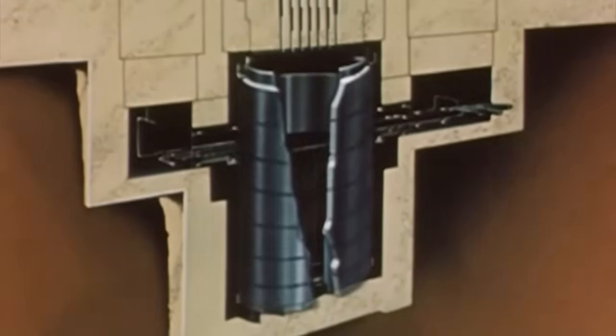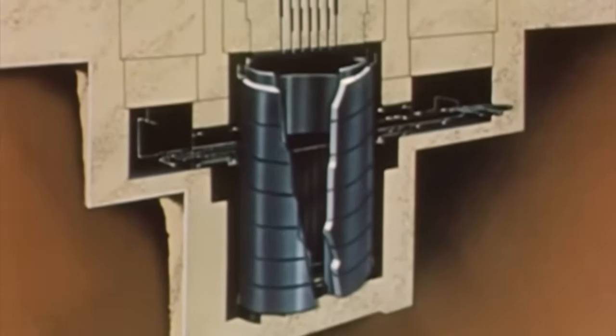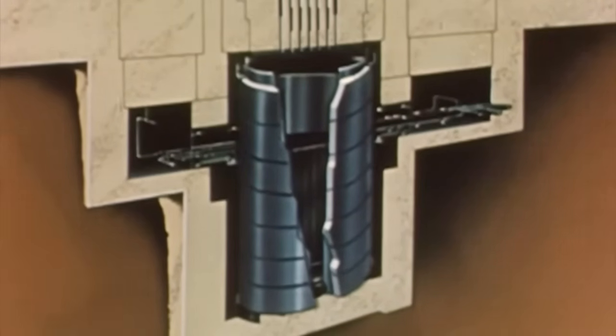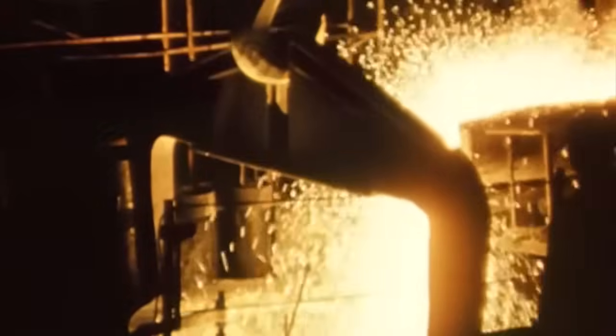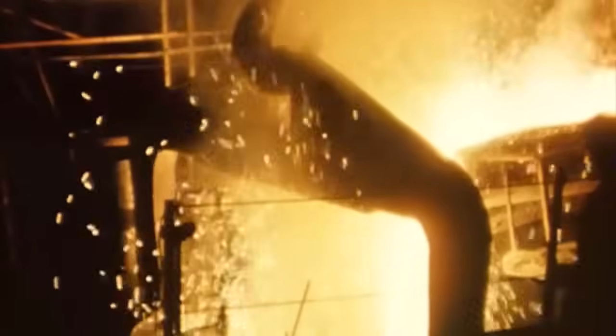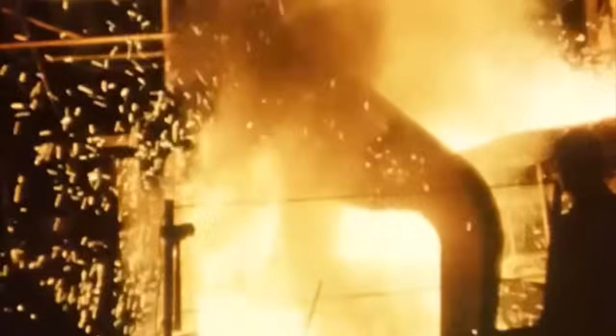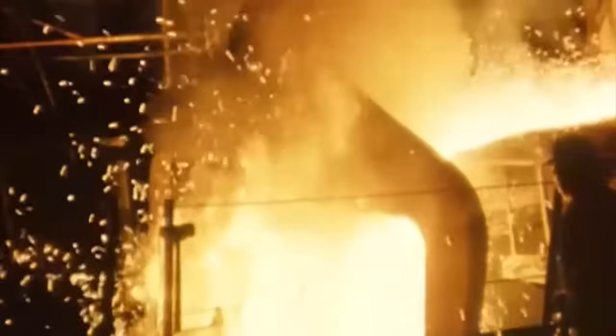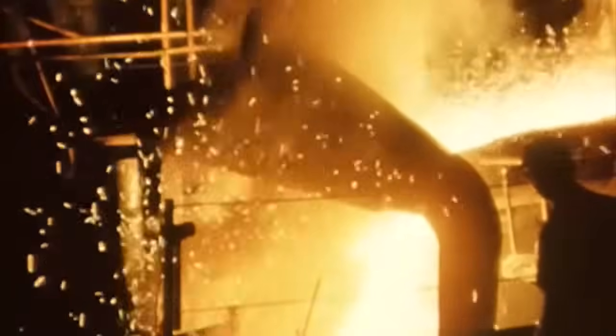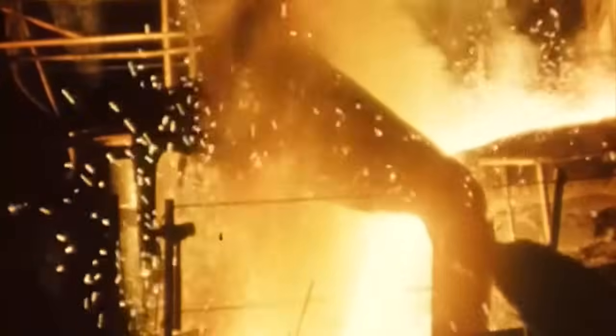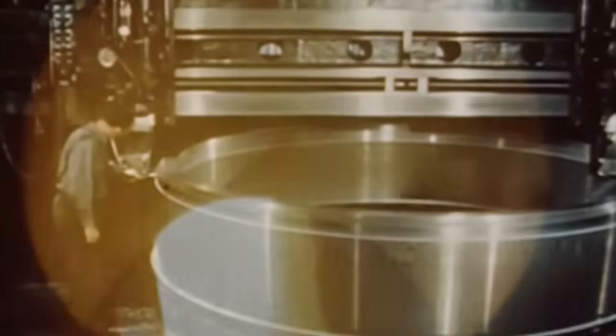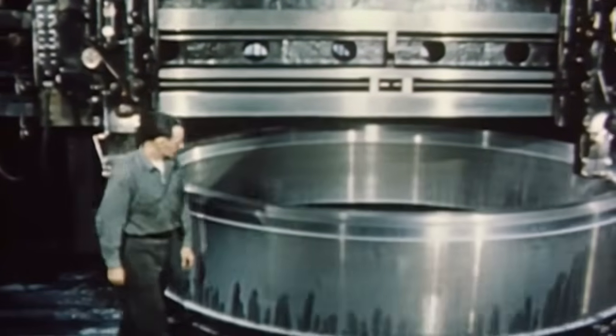Surrounding the core tank is the thermal shield. Its function is to absorb most of the heat due to gamma rays and neutrons, and to protect the concrete shield from thermal damage. It was fabricated from 1030 carbon steel, melted in an electric steel furnace. The complete shield was made up of 7 individually cast rings. Each ring was fully annealed to remove stresses in the casting, and then was machined to the specified 5.5-inch thickness.